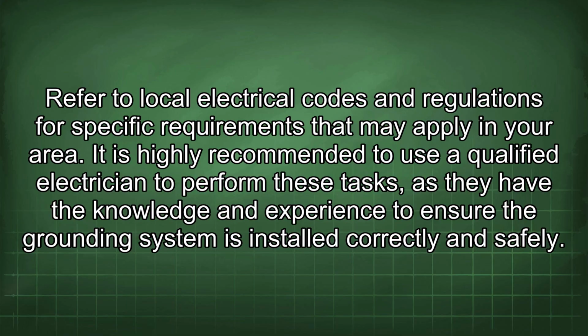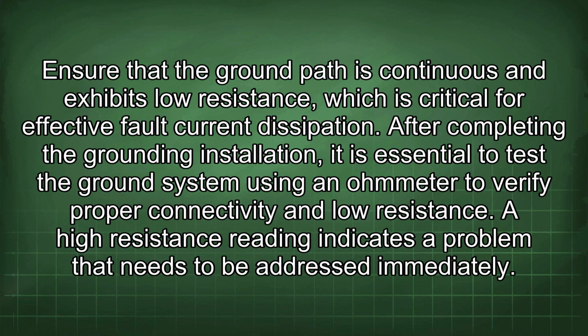It is highly recommended to use a qualified electrician to perform these tasks, as they have the knowledge and experience to ensure the grounding system is installed correctly and safely. Ensure that the ground path is continuous and exhibits low resistance, which is critical for effective fault current dissipation. After completing the grounding installation, it is essential to test the ground system using an ohmmeter to verify proper connectivity and low resistance. A high resistance reading indicates a problem that needs to be addressed immediately.